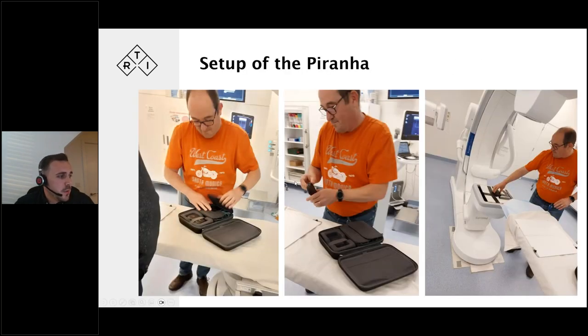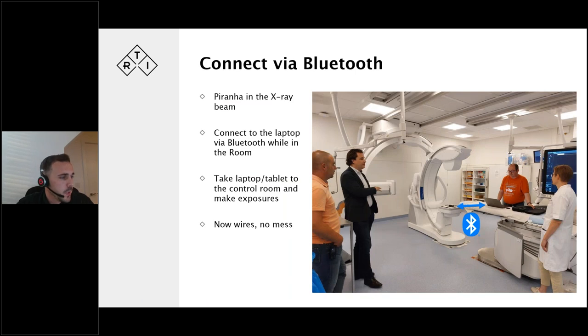To set up the Piranha, we have it in its lightweight case. We turn the Piranha on with the switch on the side, and place it into the X-ray beam. Here we have our X-ray system, the X-ray tube, and the X-ray detector. This lead shield just protects the detector from X-ray exposure as we're performing the testing. So the Piranha is nice and simple to set up in the system.